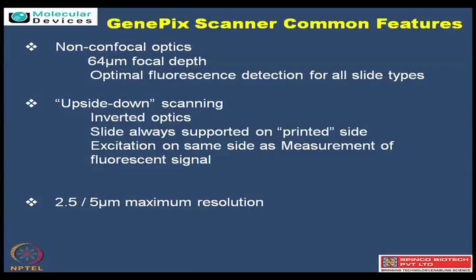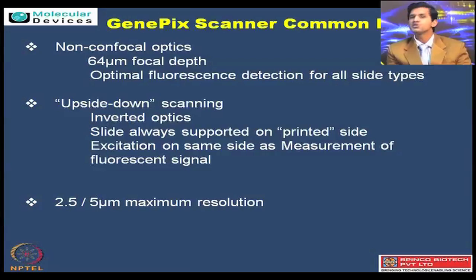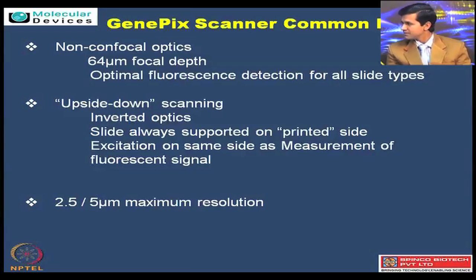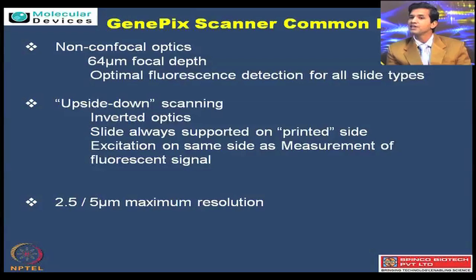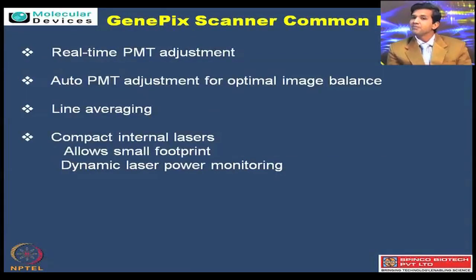If you want to use slide-based slides that have cover slips, the depth is a little bit lower, so you want to focus at a different range. In this fashion, the non-confocal optics with a focal depth of 64 microns is a major feature. Apart from that, the inverted optics - upside down - is what we are going to use, with printed sites being scanned directly and controlled for variability. The resolution at 2.5 or 5 microns, based on the system available, can also be used, along with real-time PMT adjustment.